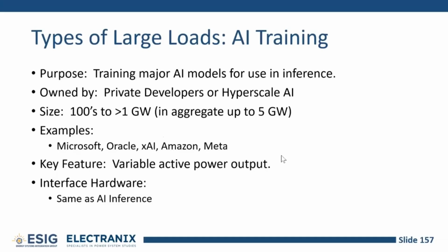So the reason why I'm distinguishing between these is because if you have a large data center coming in, what you have to worry about and how you're going to model it is going to depend on what the data center is ultimately going to be used for. Some of the folks that you talk to who are going to be building data centers don't actually know. They might be an intermediate developer type who wants to develop the capacity for a data center, and they're trying to secure the power and make sure that the infrastructure to the grid is connected, but they don't actually know what kind of load is coming in. But it really does matter if you want to model it ultimately.